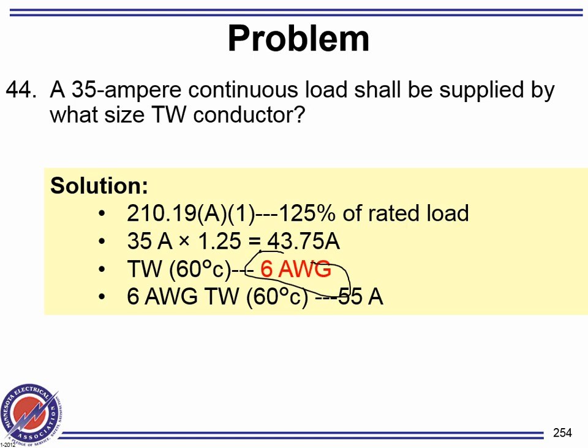All right, now I'm going to change this one to THHN. What changes if my conductor was THHN? Nothing. Why? Because in normal operating condition, you go first by the conductors, which allow me to go to 90. Then the question: am I derating? No, so I can't go to 90. Then ask yourself, do I know the lugs? No, then I can't go to 75. Is the equipment rated for more than 100 amp? No. Then I have to go to 60 anyway. So it really doesn't matter what the installation is.